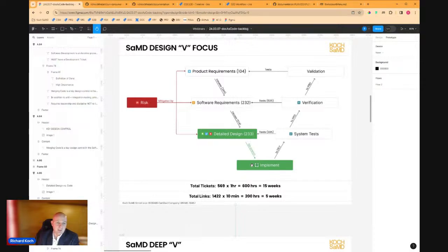And we've seen, I think recently, Philips had a recall from one of their machines. I believe it was software related, class 1 recall. There was another class 1 recall. I can't remember the product again, but we're seeing it more and more. And at least from my experience, I would say one of the root causes is the tooling that people use: document-based management systems, or even eQMS, which use documents as a unit of grouping content, doesn't work, because really it's documents with metadata. And you need to move to more agile, more project overview, where you can see everything in one go. Critical to safety is traceability.